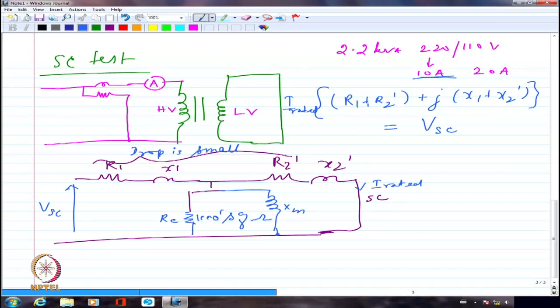So normally, this is IC and this is IM, which put together make up my no load current, and the no load current is less than 5%. So I really do not have to take that into consideration. When 10 ampere is flowing through the primary winding, this may be 0.4 or 0.3 or something like that. I don't have to worry so much about taking that into account. That's the reason why I'm neglecting it.